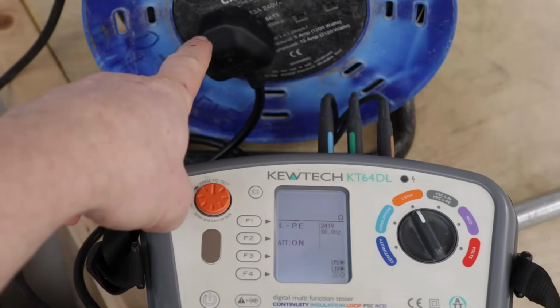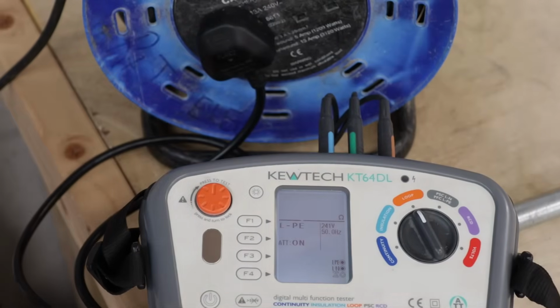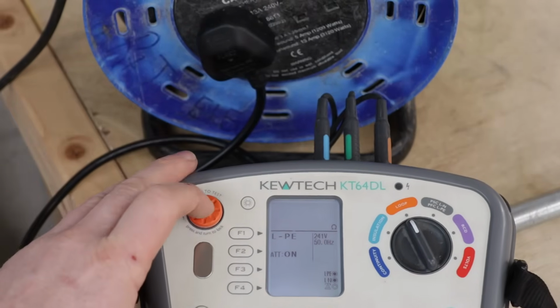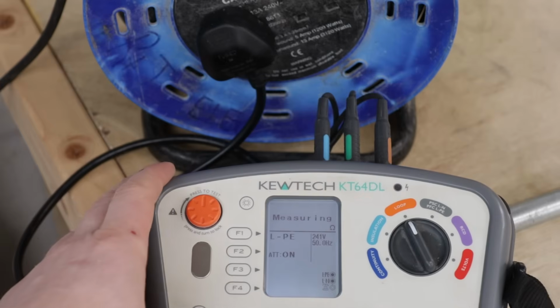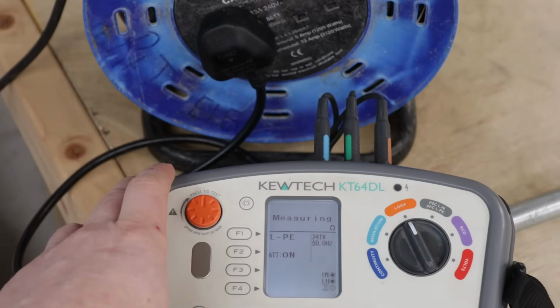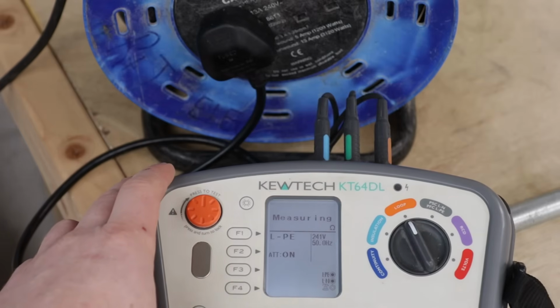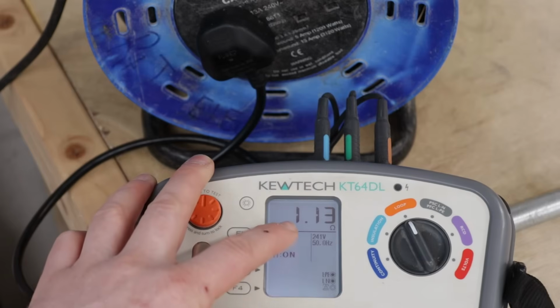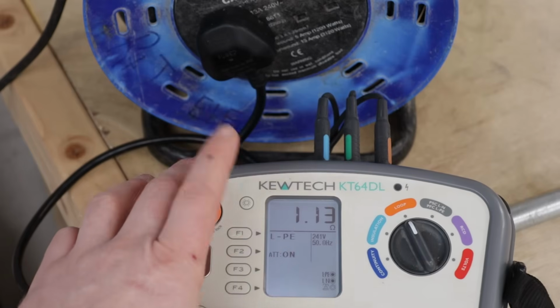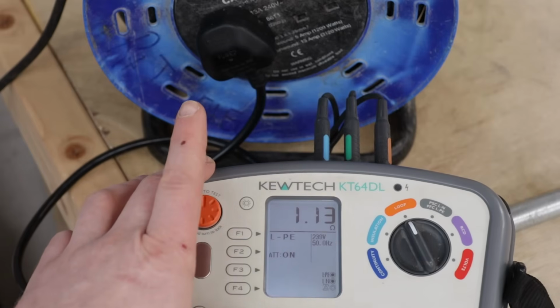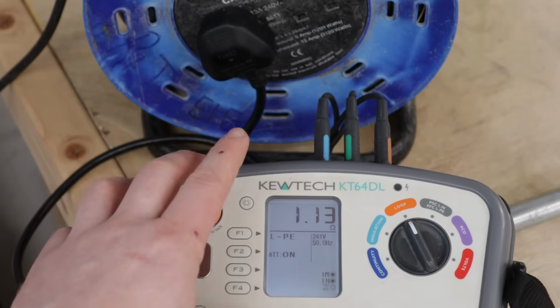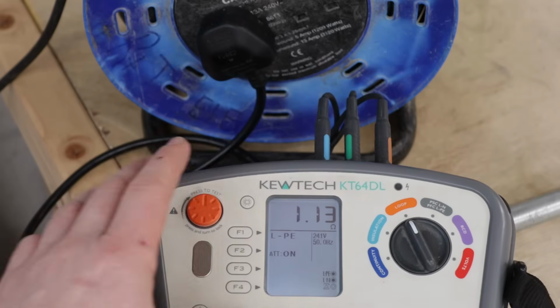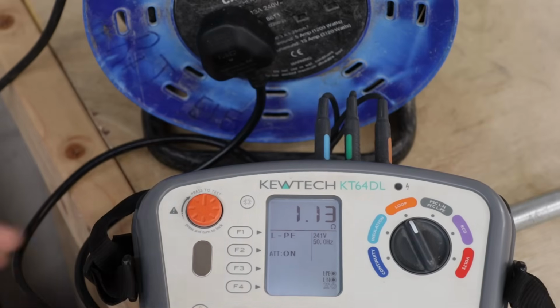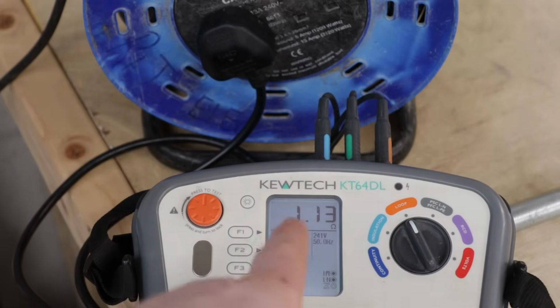Hey guys, now I'm plugged into my extension lead. So my extension lead is plugged into that socket and I'm now plugged into this extension lead. So if I do my loop impedance test again, we'll see how much resistance this extension lead adds to the circuit. So there you go, we've almost doubled the resistance of the circuit just by adding the extension lead. So you can see they can add quite a lot. The cable on this extension lead is quite small. I've oversized my socket cable. I've also oversized my mains cable to keep that loop impedance low. So you can see I've doubled the resistance of the circuit just by adding one extension lead.